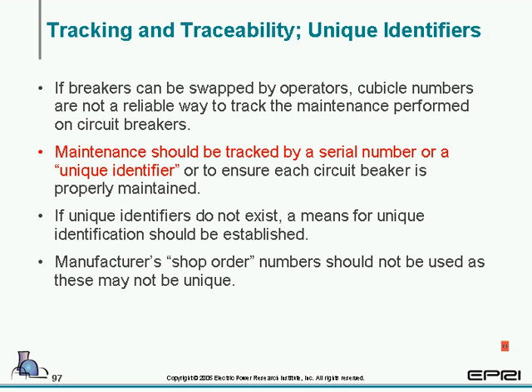First off, tracking and traceability. We learned kind of the hard way in the nuclear industry that just because a breaker has a number on it doesn't mean it's a unique identifier. And a lot of times it is. A breaker may have a serial number, and if it does, that's fine. You can track the maintenance by serial number of the breaker.